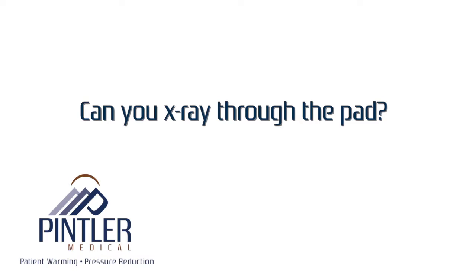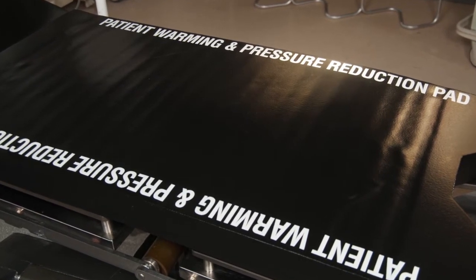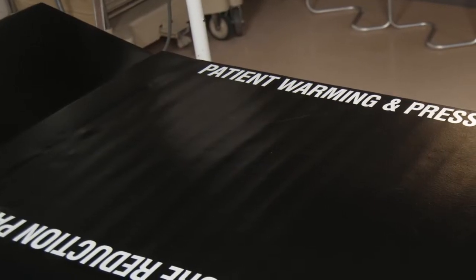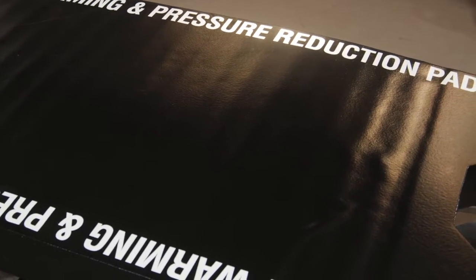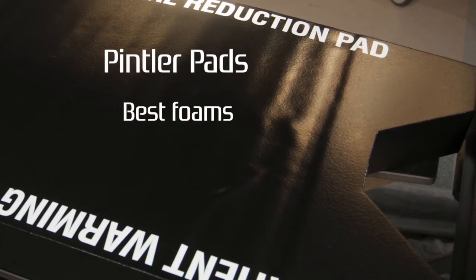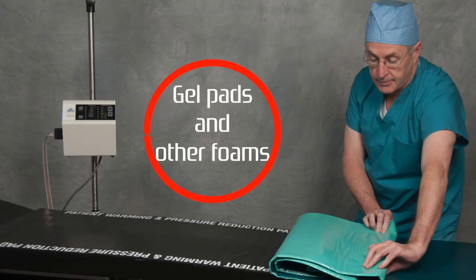Can you x-ray through the pad? Yes, it is an integral part of the design. The ink is the secret — it is x-ray transparent. What is pressure reduction and how does it work with the Pintler patient warming system? Pressure reduction is dispersal of patient body weight over the broadest surface possible. The goal is to reduce pressure points that can damage tissue. In the Pintler pads, the best foams and pressure reduction design is applied to achieve the best pressure reduction results. We do not recommend using gel pads or other foams over the Pintler pad, as they don't enhance pressure reduction.